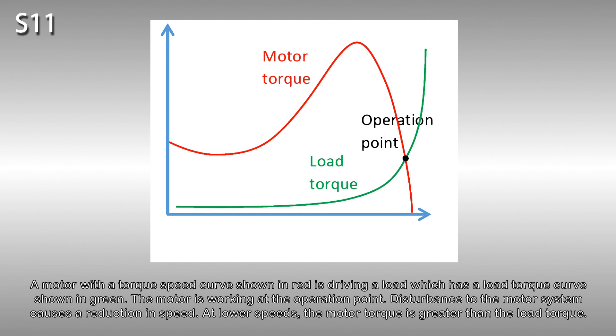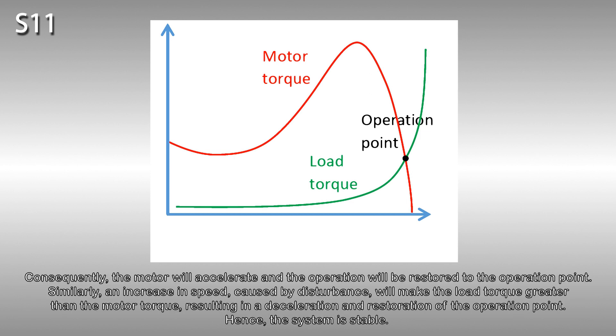A motor with a torque speed curve shown in red is driving a load which has a load torque curve shown in green. The motor is working at the operation point. Disturbance to the motor system causes a reduction in speed. At lower speeds, the motor torque is greater than the load torque. Consequently, the motor will accelerate and the operation will be restored to the operation point. Similarly, an increase in speed caused by disturbance will make the load torque greater than the motor torque, resulting in a deceleration and restoration of the operation point. Hence, the system is stable.